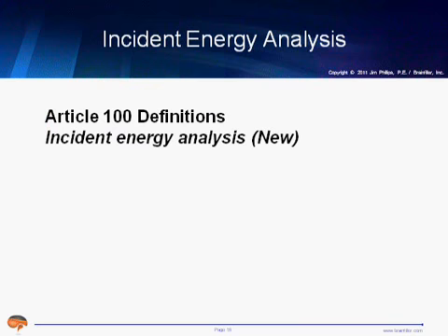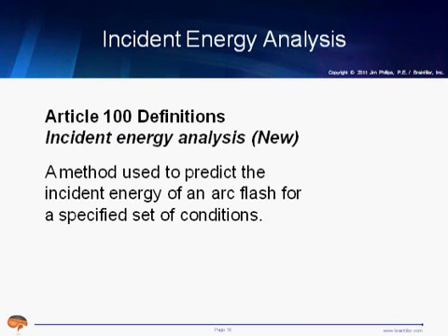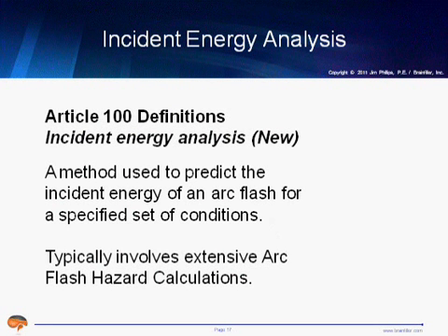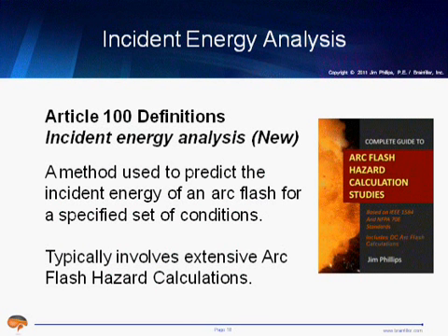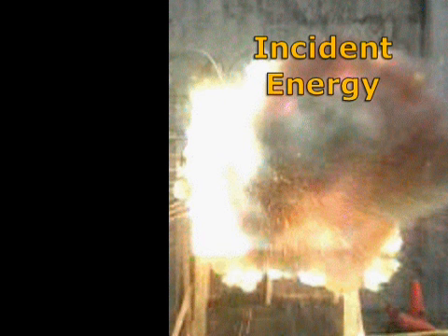And the definition, according to NFPA 70E, is a method to predict incident energy from an arc flash for specific conditions. Now, there's a lot that actually goes into this. I know many of you are involved in arc flash studies, arc flash calculation studies, and the studies typically involve some pretty extensive calculations. Fortunately, there are a lot of good software packages out there that help along, but it can still be quite a complex undertaking. Knowing how to model the system, knowing what conditions you need to model. And so we now have a definition that helps it along.